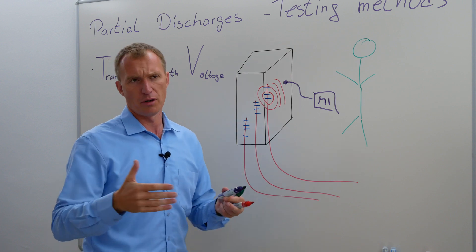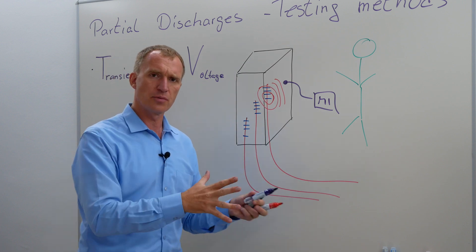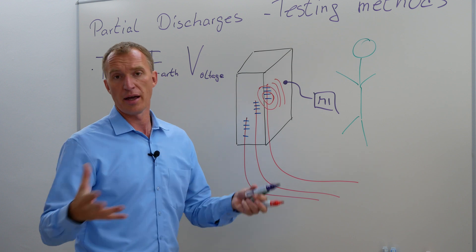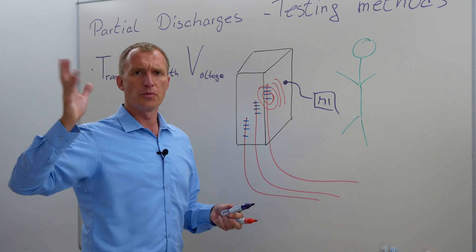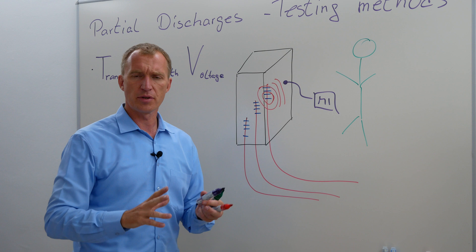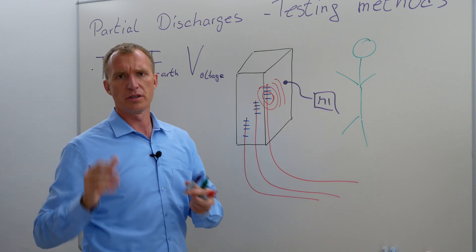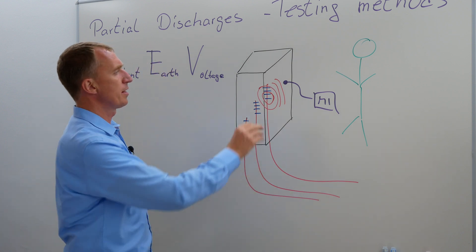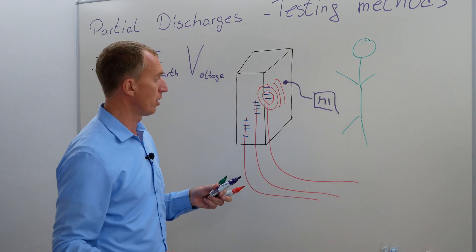Sometimes they work in the megahertz range, usually not where the IEC 60270 would expect you to measure, but at two, three megahertz they're usually starting. Sometimes they go up to 50, 70, sometimes even 100, and that gives you a possibility to figure out are there partial discharges or not.